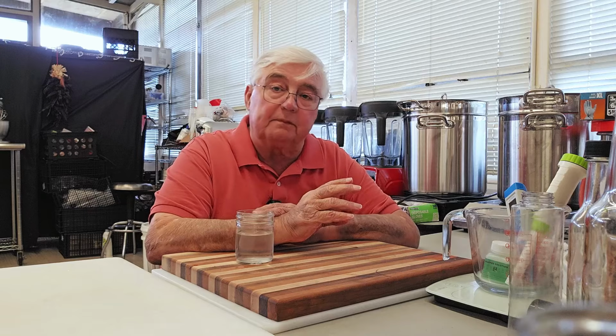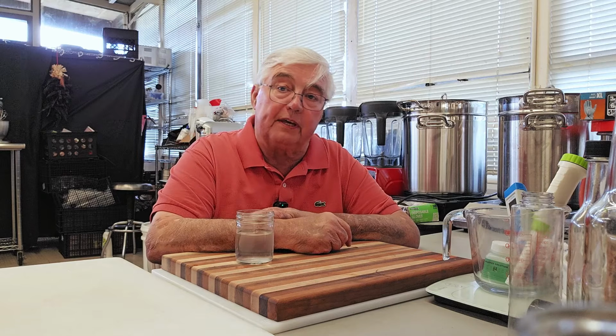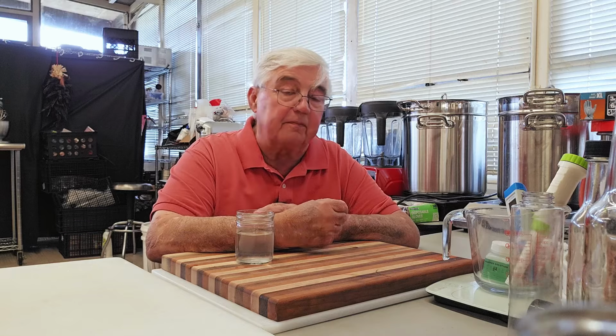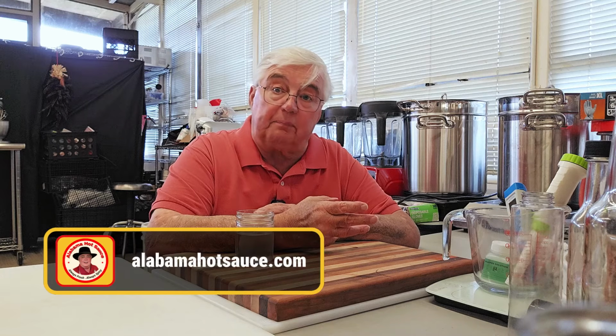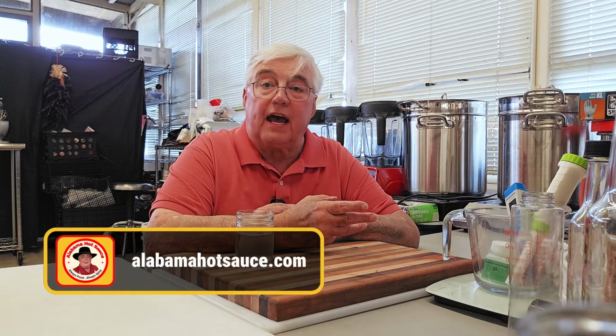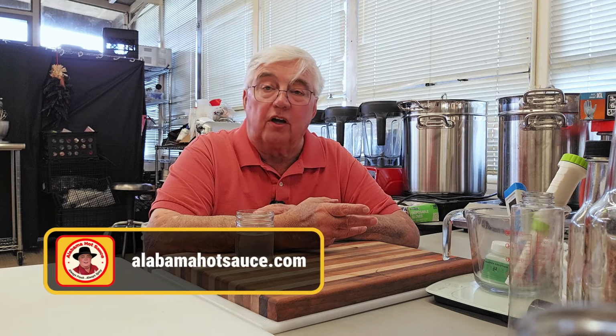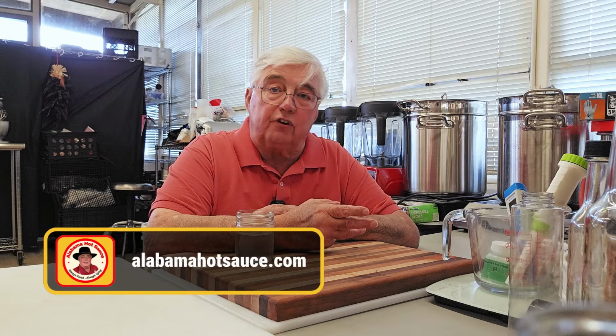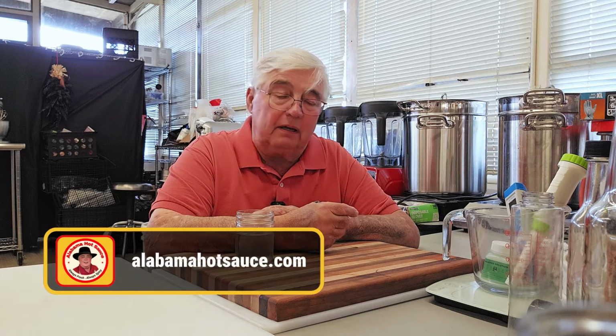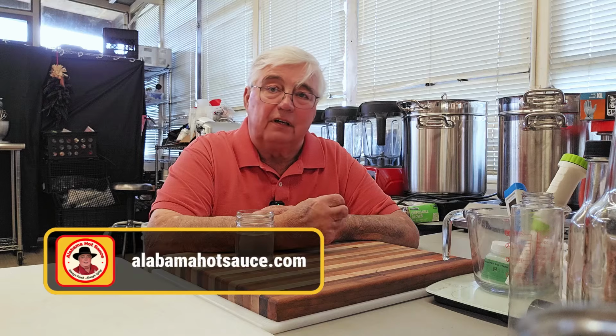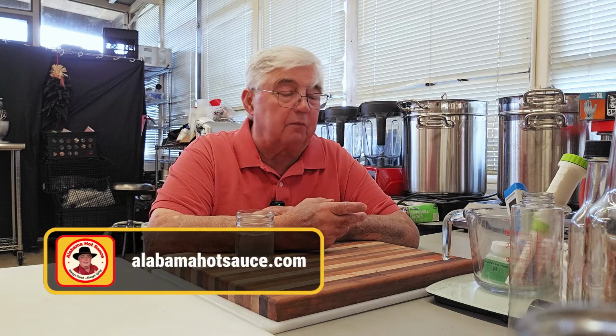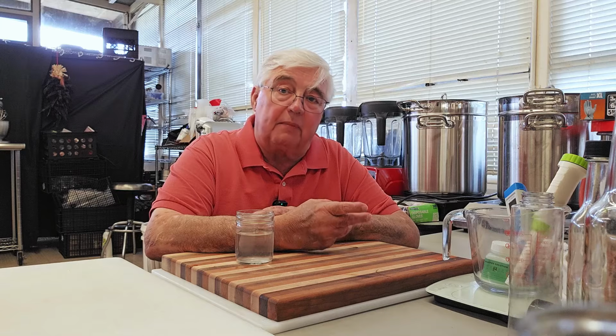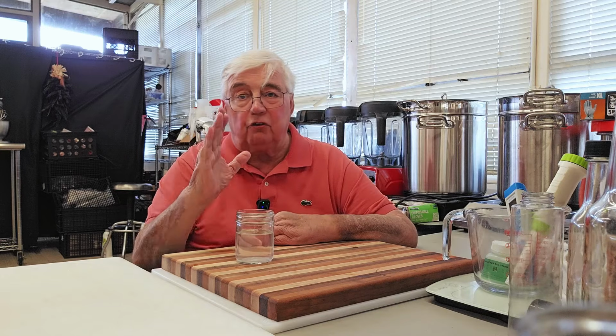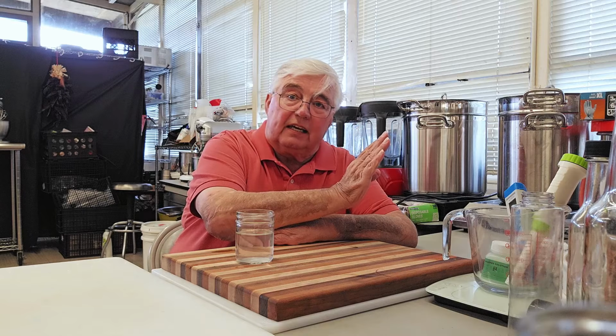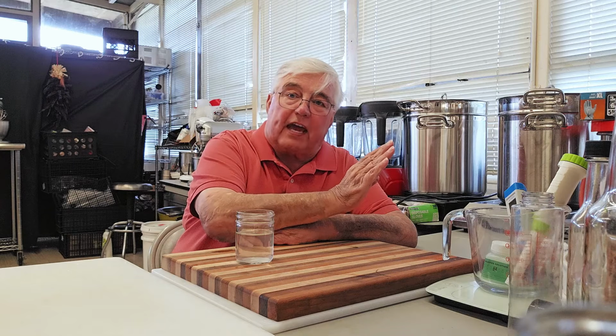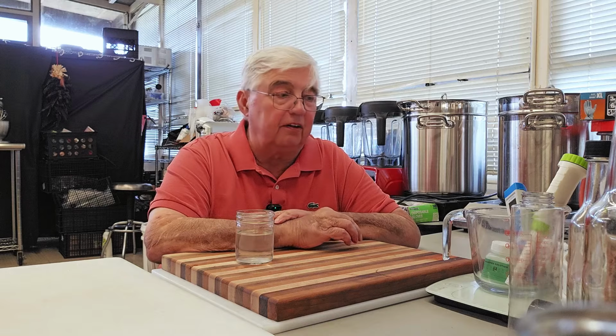It's also important to point out that tomorrow, that calibration will still be there. And the day after, and the day after. I've tested pH meters where I go as much as a month or a month and a half in between calibrations. They work just as good. The only reason you calibrate is because things can happen. You can bang them around. You can have little fluctuations in the battery power, which throw it off calibration. So we calibrate mostly to check them to make sure that they're reading at neutral and at acidity, at least within a reasonable degree of accuracy. And that is simply all there is to it.